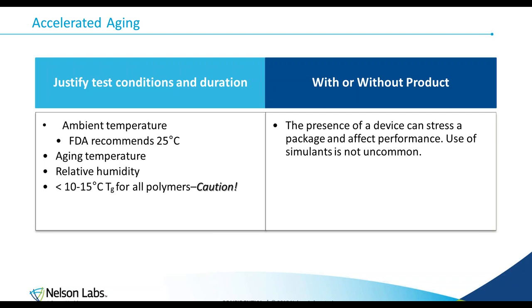As far as the ambient temperature, FDA recommends 25 degrees C. The aging temperature, as I mentioned, the most common one is 55 degrees C. You can go up to 60 degrees C, but the standard recommends not exceeding 60 degrees Celsius.